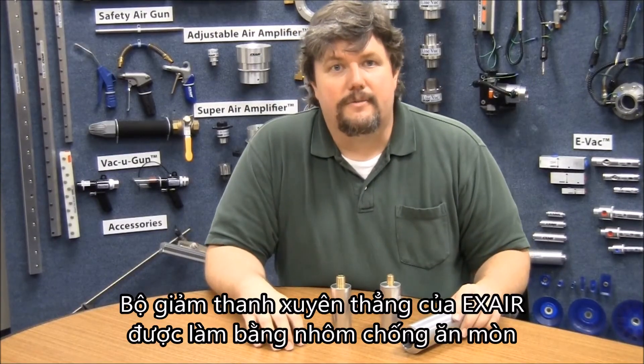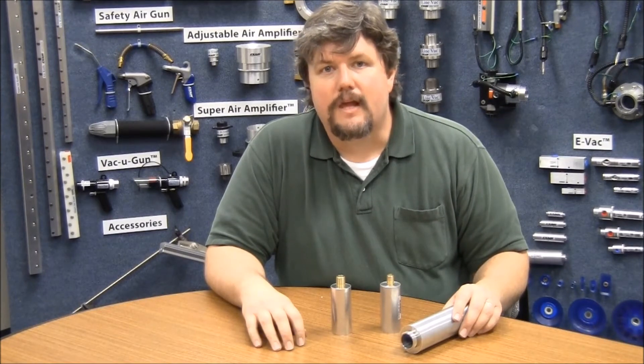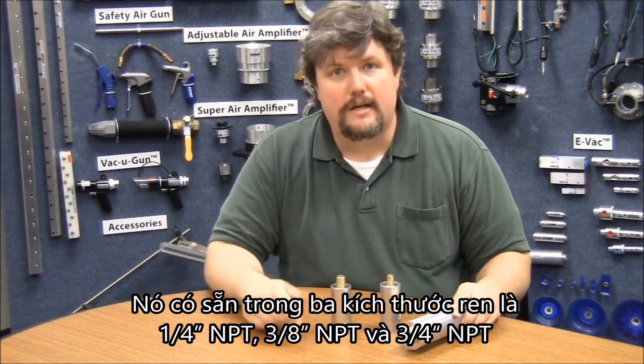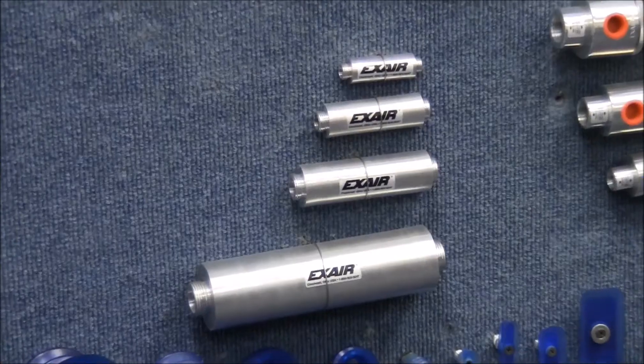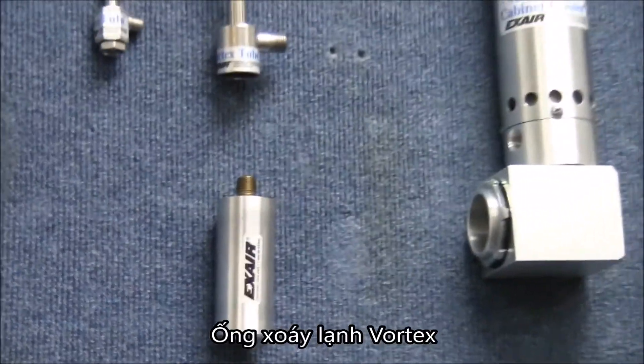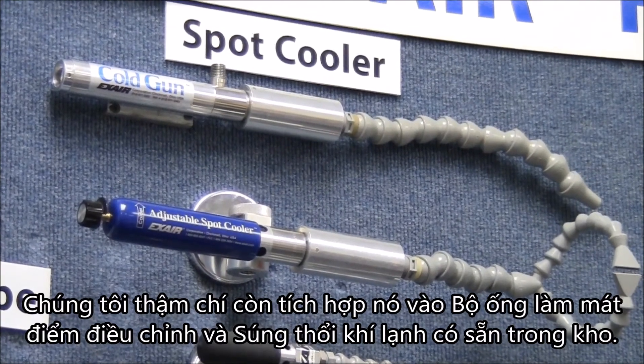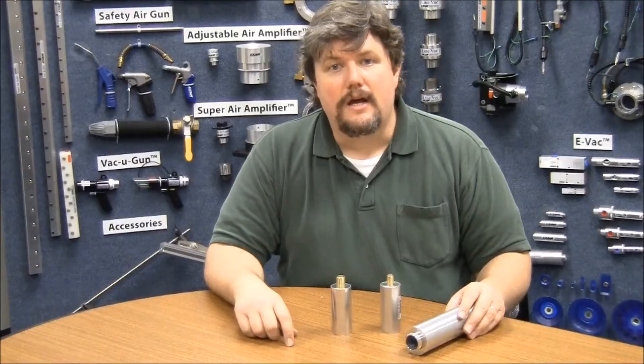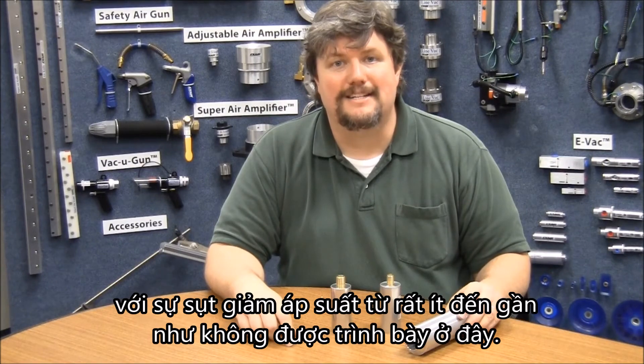EXAIR straight-through mufflers are made of corrosion resistant aluminum and are lined with sound absorbing foam. They're available in three sizes with quarter inch NPT, 3/8 inch NPT, and 3/4 inch NPT threads, male on one end, female on the other. These are also commonly used with our evac vacuum generators, our vortex tubes, and our cabinet cooler systems. They're even incorporated into our adjustable spot coolers and cold gun air coolant systems from stock. They can provide noise reduction of up to 20 decibels with little to no pressure drop, as demonstrated here.